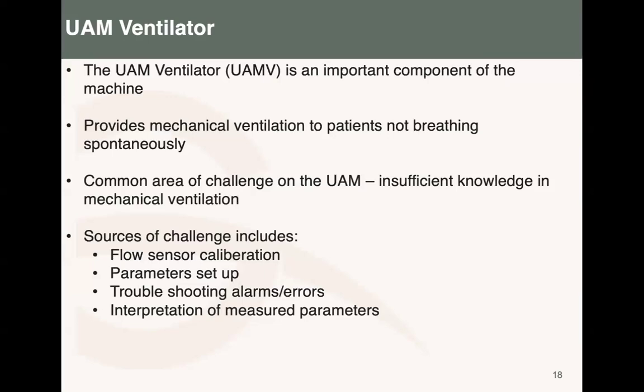Most places where the UAM is used have no critical care and no ventilator, so there's a bit of a challenge with mechanical ventilation, and that's reflected when using the UAMV. But in our training, this is an area we always emphasize, making sure users have enough knowledge to use the machine, since we know it's one of the key features. Experience has shown there are a few challenges, mainly with flow sensor calibration.